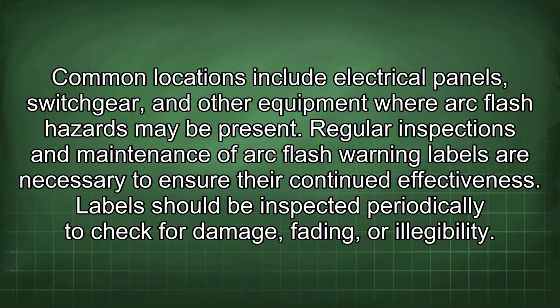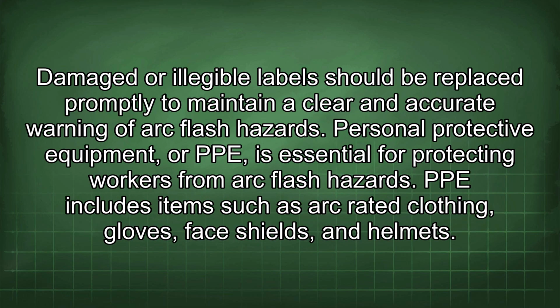Regular inspections and maintenance of arc flash warning labels are necessary to ensure their continued effectiveness. Labels should be inspected periodically to check for damage, fading, or illegibility. Damaged or illegible labels should be replaced promptly to maintain a clear and accurate warning of arc flash hazards.